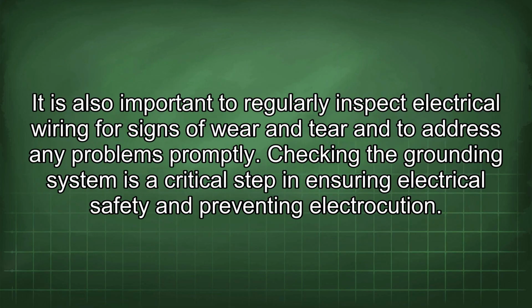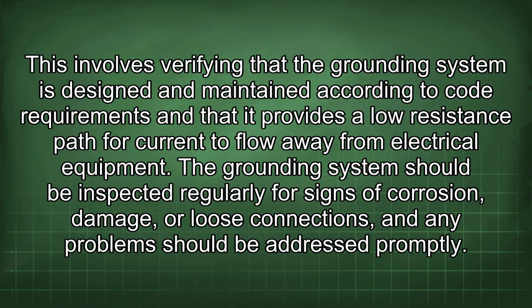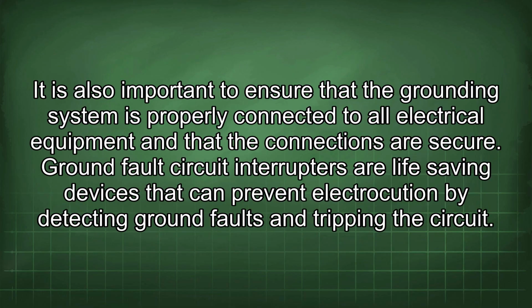It is also important to regularly inspect electrical wiring for signs of wear and tear and to address any problems promptly. Checking the grounding system is a critical step in ensuring electrical safety and preventing electrocution. This involves verifying that the grounding system is designed and maintained according to code requirements and that it provides a low resistance path for current to flow away from electrical equipment. The grounding system should be inspected regularly for signs of corrosion, damage, or loose connections, and any problems should be addressed promptly. It is also important to ensure that the grounding system is properly connected to all electrical equipment and that the connections are secure.